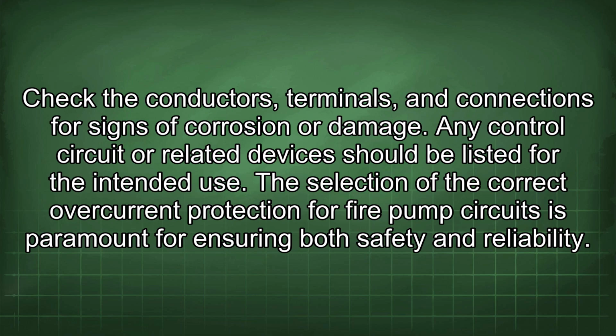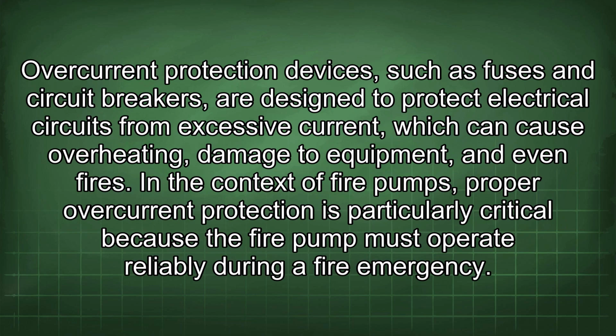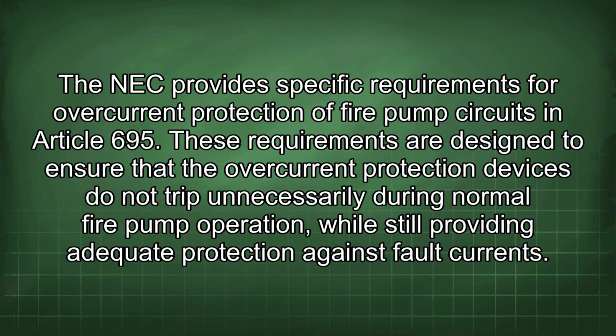The selection of the correct overcurrent protection for fire pump circuits is paramount for ensuring both safety and reliability. Overcurrent protection devices, such as fuses and circuit breakers, are designed to protect electrical circuits from excessive current, which can cause overheating, damage to equipment, and even fires. In the context of fire pumps, proper overcurrent protection is particularly critical because the fire pump must operate reliably during a fire emergency. The NEC provides specific requirements for overcurrent protection of fire pump circuits in Article 695. These requirements are designed to ensure that the overcurrent protection devices do not trip unnecessarily during normal fire pump operation while still providing adequate protection against fault currents.